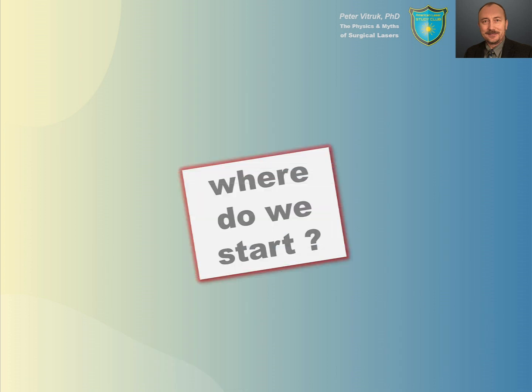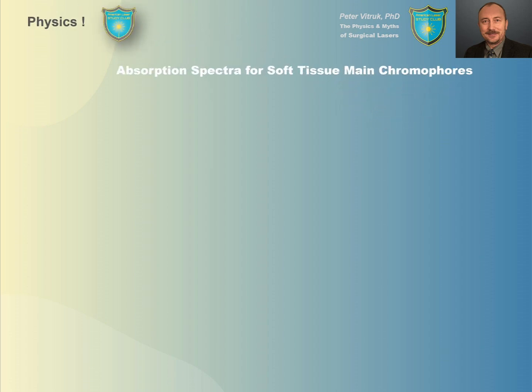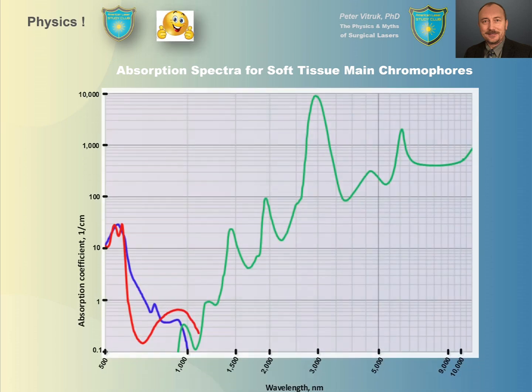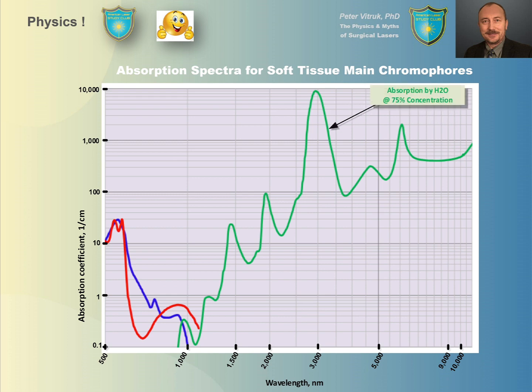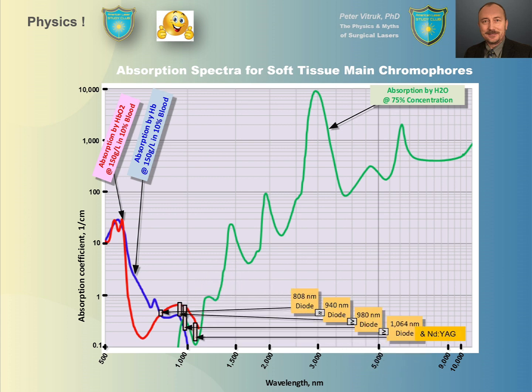To answer where specific lasers belong on the map, we need to look at the physics of laser-tissue interaction — specifically the optical properties and the absorption spectrum for the main soft tissue chromophores. Here is the absorption spectrum for water at a histologically relevant concentration of 75%, and for oxyhemoglobin at a histologically relevant blood presence of 10%. Now let's place all of the diode and neodymium YAG lasers on this chart.